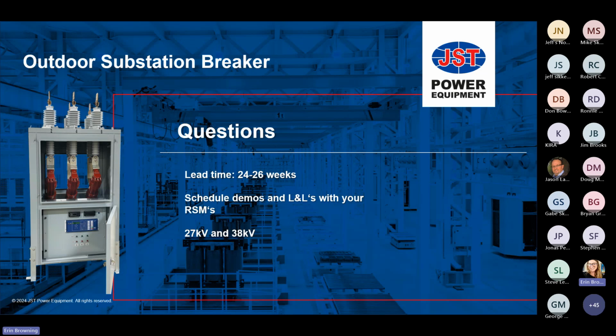I know you guys are anxious about the 27 and 38 kV designs. I can tell you that both of those are underway. The 27 kV is essentially going to be the same breaker. The pole is already rated 27 kV, so it's a matter of meeting the BIL ratings, which are 150 kV BIL at that level. So we're taking some measures to change out the bushings and make sure we have the dielectric distances that we need between phases. We're basically adapting our 15 kV breaker to 27 kV.